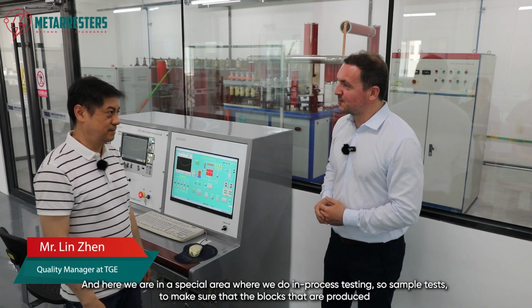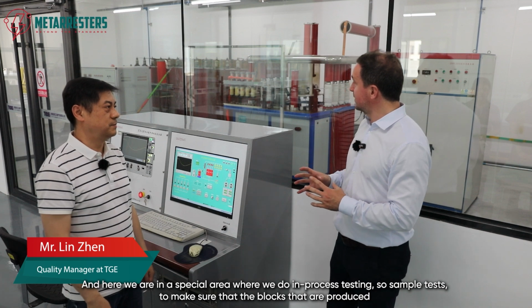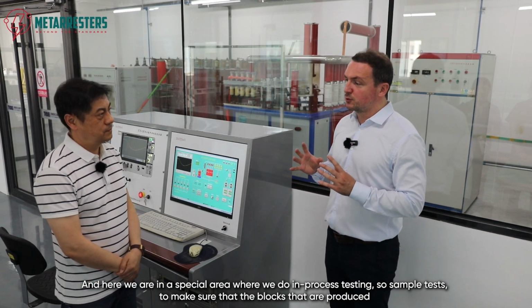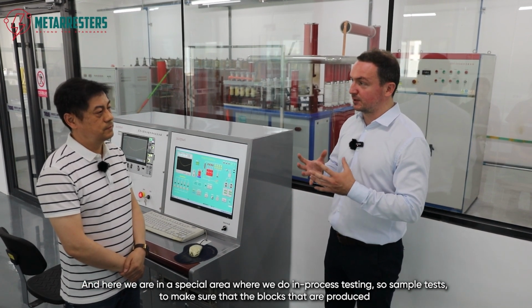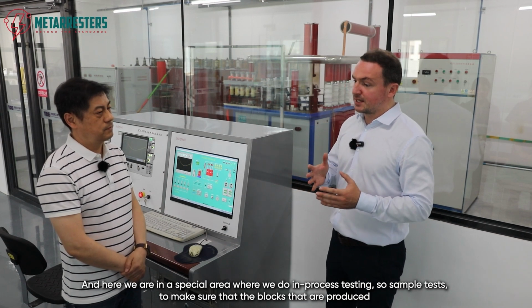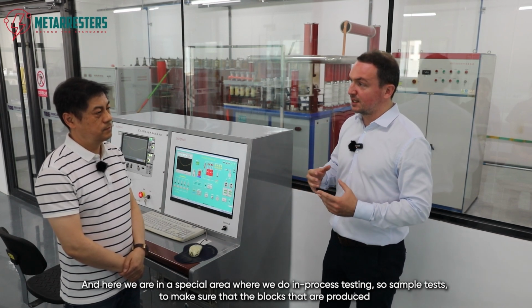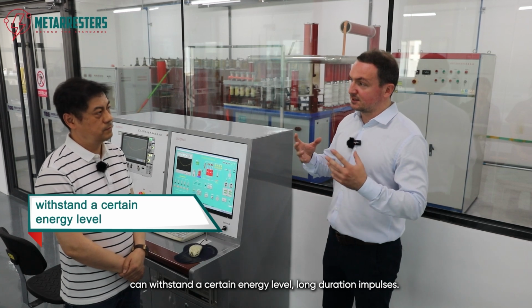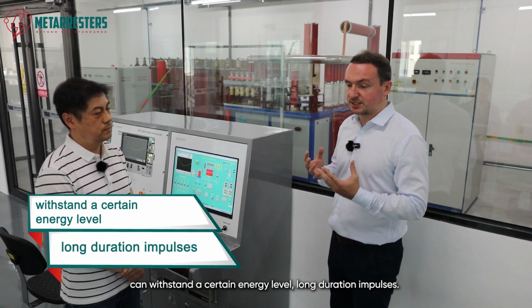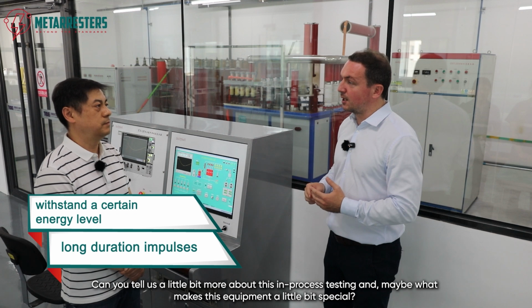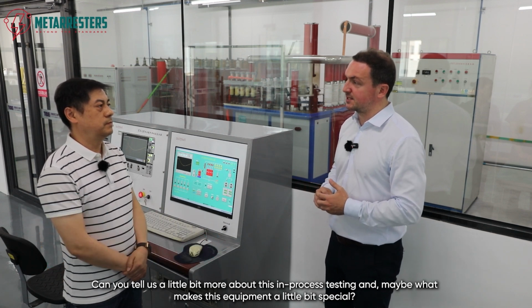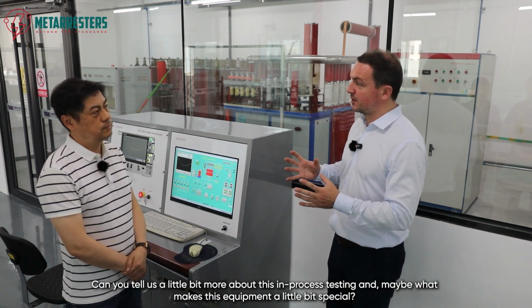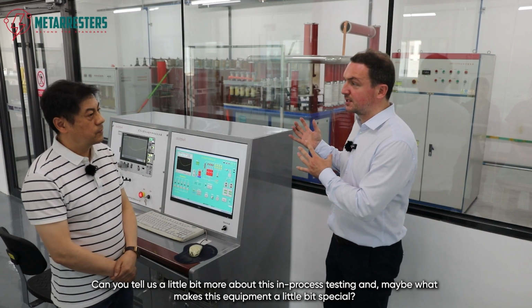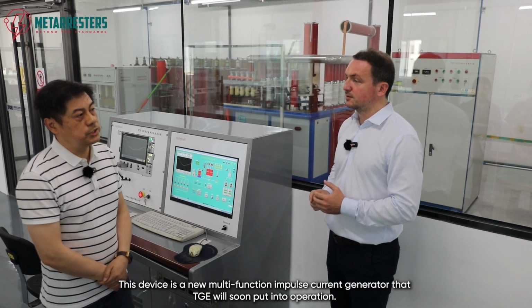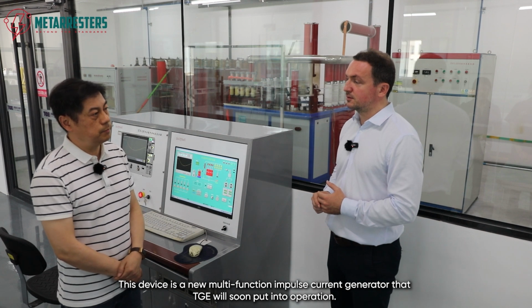Nice to meet you. So you're the quality manager at TGE. Yeah. And here we are in a special area where we do in-process testing. So sample tests to make sure that the blocks that are produced can withstand a certain energy level, long duration impulses. Can you tell us a little bit more about this in-process testing and maybe what makes this equipment a little bit special? This device is a new multifunction impulse current generator that TGE will soon put into operation.